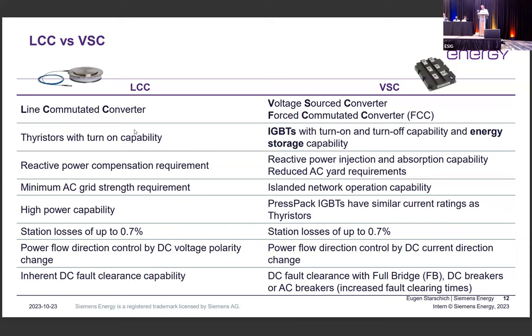A few years ago, there was a big issue: if we want to have high power, anything above 2 gigawatts, we need to go with the LCC. I think this is also obsolete. We have new IGBT technology, so-called press-pack IGBTs, freely available on the market, which have similar current ratings as thyristors. So there is actually no limit for the VSC technology anymore. What we managed with the VSC is also to reduce the losses, so we are now in the same losses range as the LCC technology.